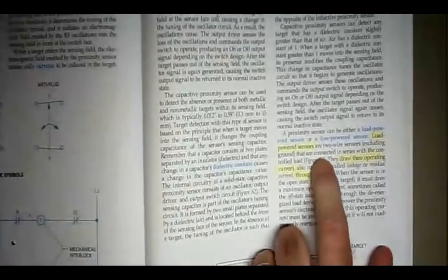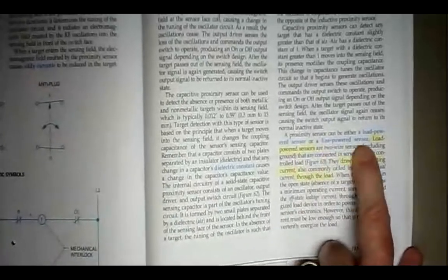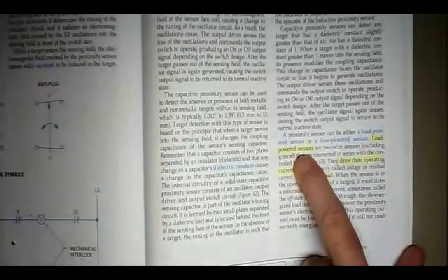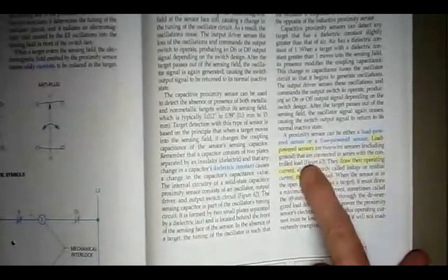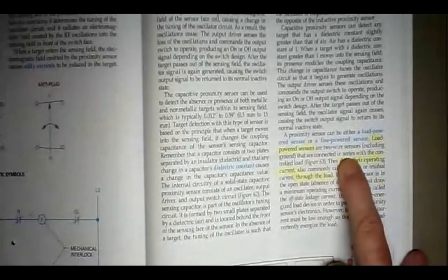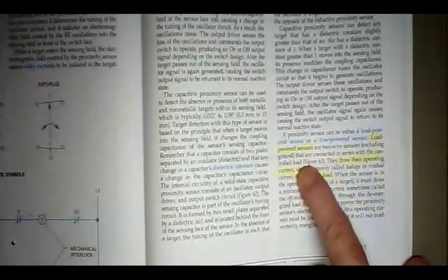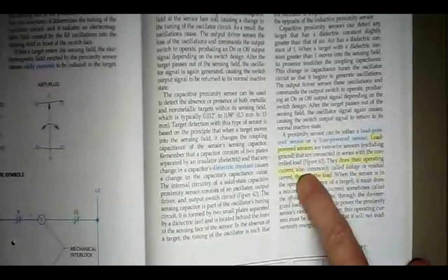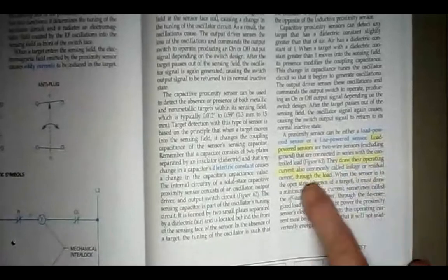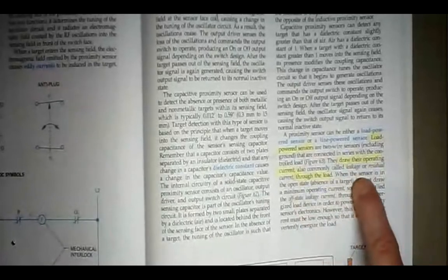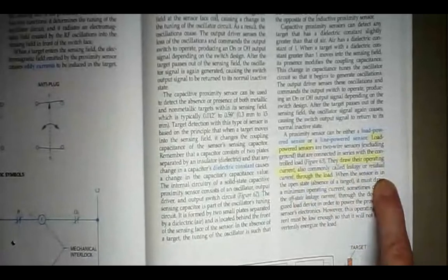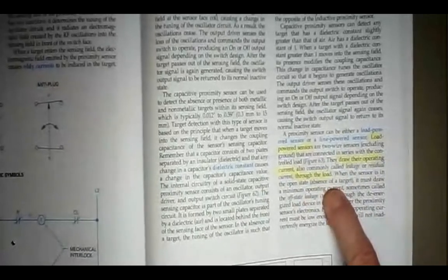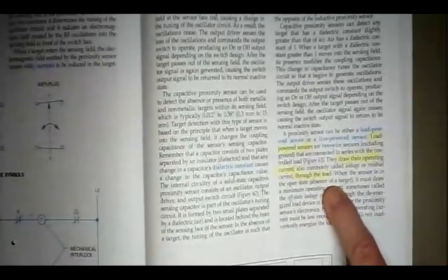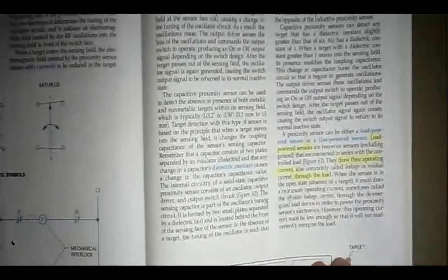Down here on page 51, right-hand side, bottom of the page, it says a proximity sensor can be either a load-powered sensor or a line-powered sensor. Load-powered sensors are two-wire sensors excluding the ground that are connected in series with the controlled load. They draw their operating current, also commonly called the leakage or residual current, through the load. So load-powered sensors get their power through the load.